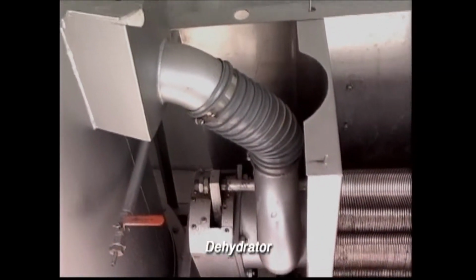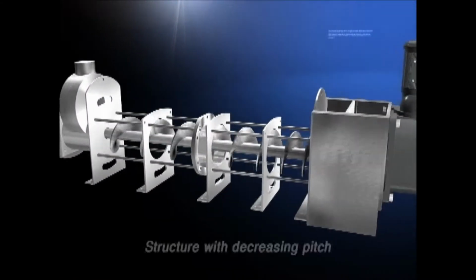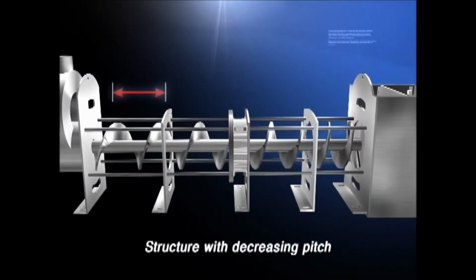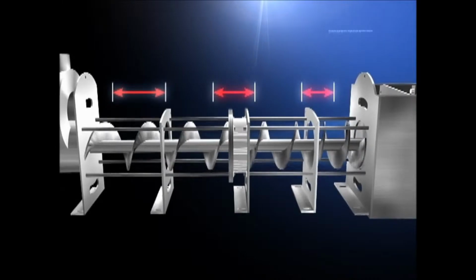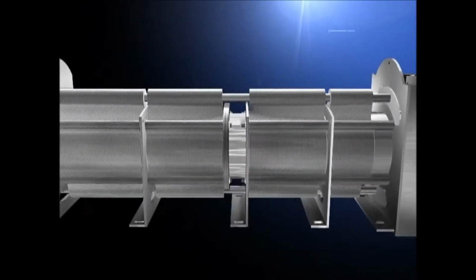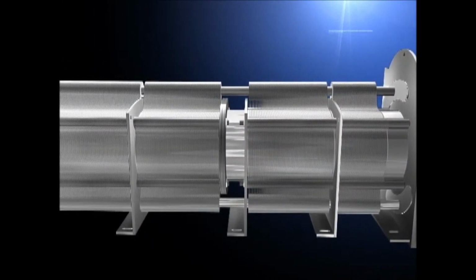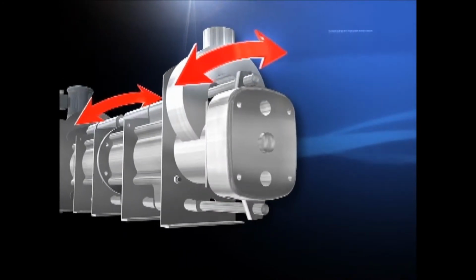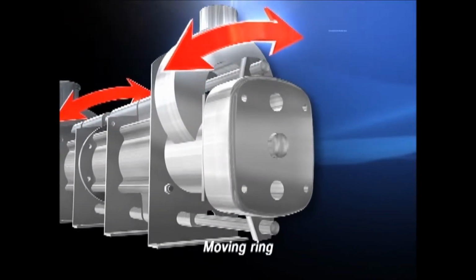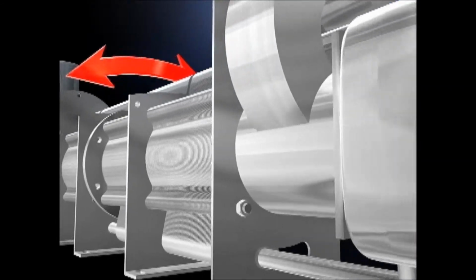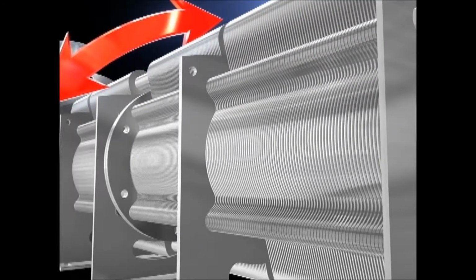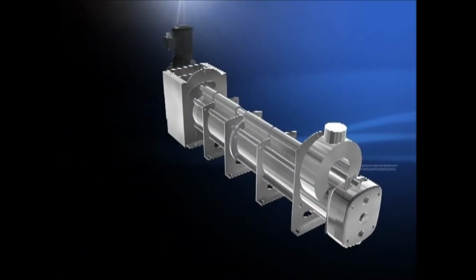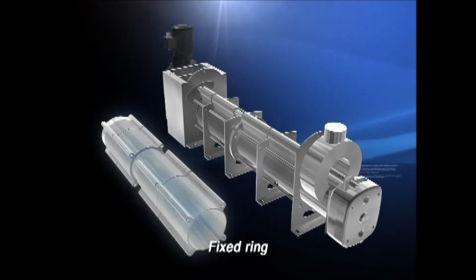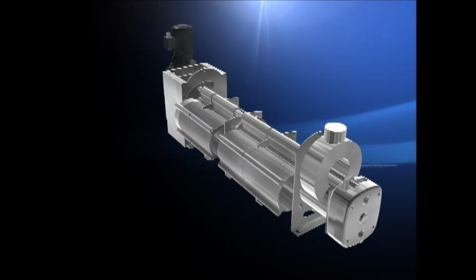In the dehydration facility, while the sludge flowing through an inlet is moved constantly by a pitch-reduced screw, the residue fluid is discharged through a gap-reduced filtration part. Unlike other screw-equipped dehydrators, the moving ring driven by a rod for pendulum motion located at the gearbox on both sides of the screws, and the ring fixed to a support beam, which maintains the shape of the dehydrator, are laminated in the middle of washers.